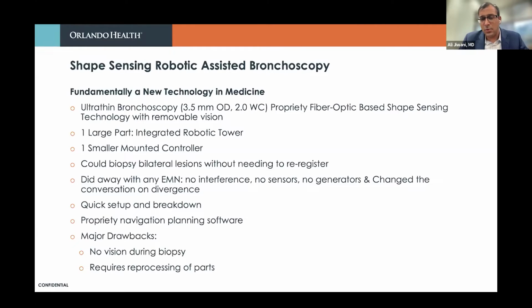Because there are no EM fields, it didn't have those drawbacks: no generators, no sensors, no interference. And so if you wanted to do bilateral lesions, you didn't have to re-register. You could bring the scope out of the body and put it back in, and there was no need for re-registration, cutting down on time and complexity. Now, the shape sensing technology also changed the conversation on divergence, so we're going to come back to that in a little bit. Setup for this is relatively quick, breakdown is even quicker. And it had its own proprietary navigation planning software that was different than the other EMs, which we'll come back to as well.